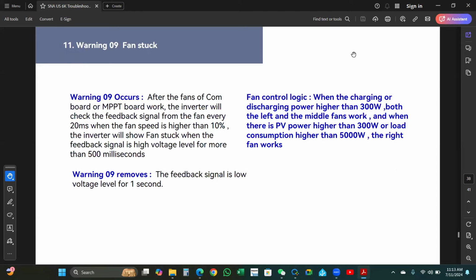Number 11, warning 09, fan stuck. Warning 09 occurs after the fan of the COM board or MPPT board works. The inverter will check the feedback signal from the fan every 20 milliseconds. When the fan speed is higher than 10%, the inverter will show fan stuck when the feedback signal is high voltage level for more than 500 milliseconds. Warning 09 removes when the feedback signal is low voltage level for 1 second.